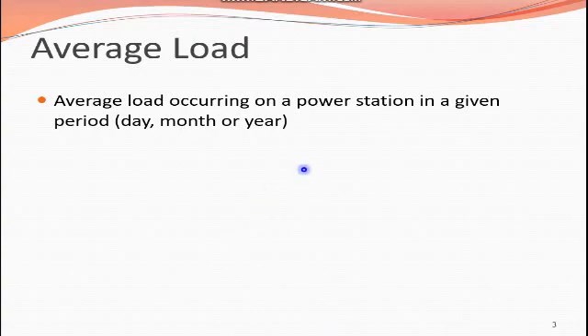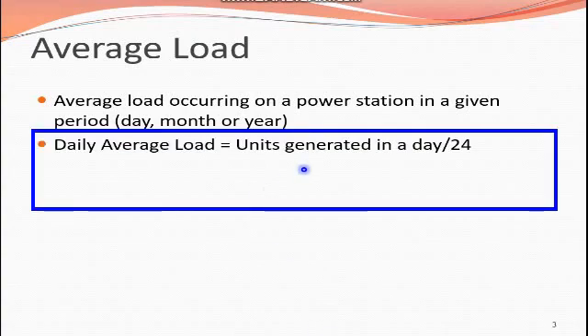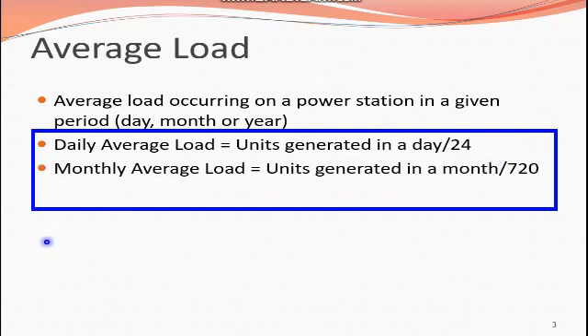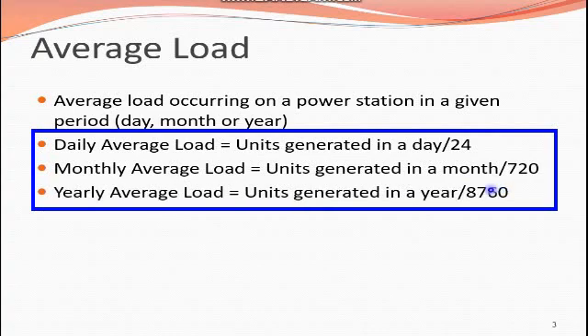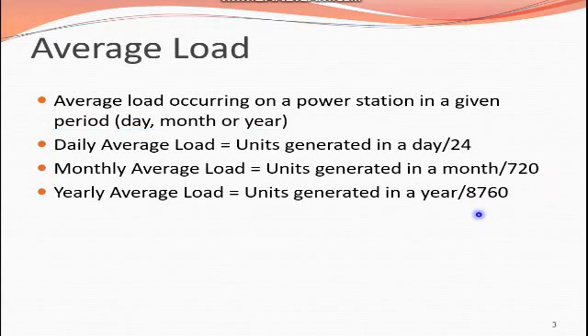There are different formulas for average load. Daily average load is equal to units generated in a day divided by 24 hours. Monthly average load is equal to units generated in a month divided by 720 hours. Yearly average load is equal to units generated in a year divided by 8760 hours. You can calculate it according to your requirements.